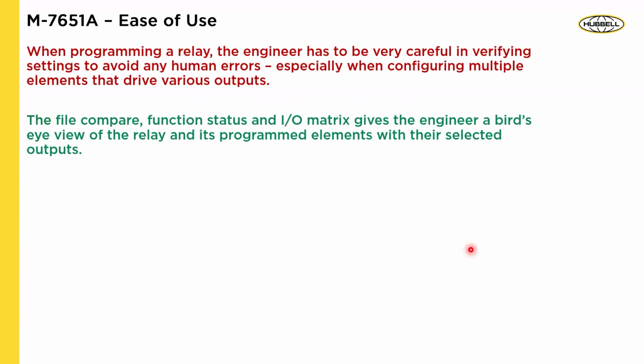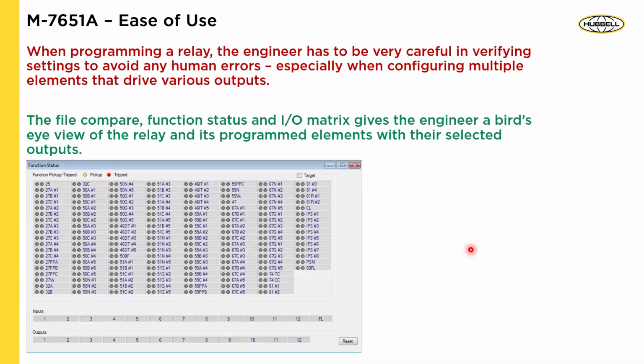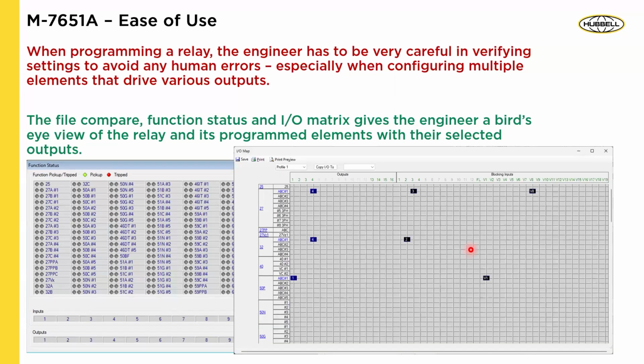The other challenge we see is you have to be very careful in reviewing the settings to avoid human errors, especially when configuring multiple elements that drive various outputs. So what we do is we give you a bird's eye view of the programmed elements and their selected outputs. So this is a function status, right? So you know right off the bat which ones are picking up, which ones are tripped, which ones are blinking, and you'll see the inputs and output statuses right there.